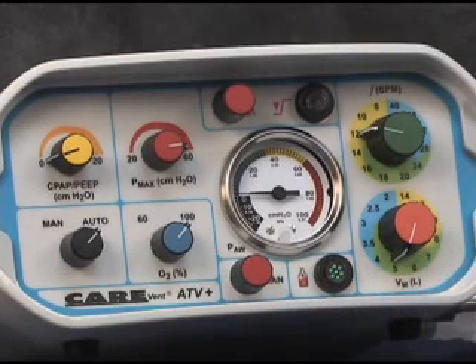Should the rescuer stop manually ventilating, there will be a delay of 20 seconds before automatic ventilations recommence, without any intervention by the rescuer being required. The 20-second delay is calibrated to allow the ventilator to be used during mask-ventilated CPR, with 20 seconds being sufficient time for 30 chest compressions to be provided.